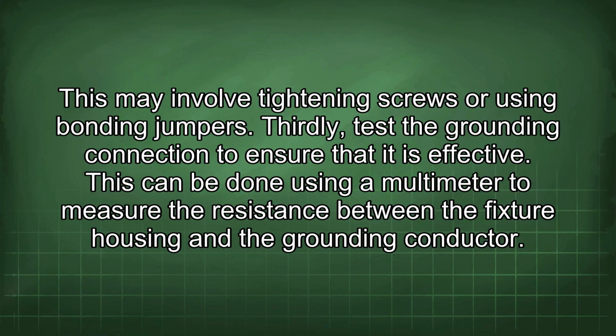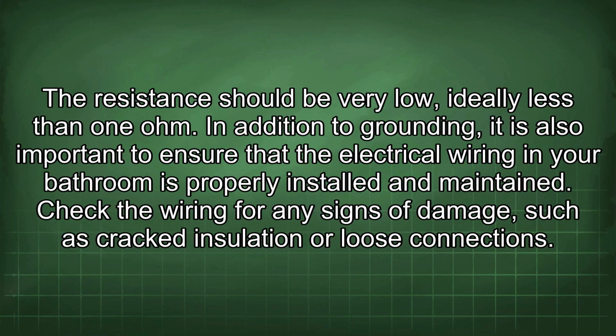Thirdly, test the grounding connection to ensure that it is effective. This can be done using a multimeter to measure the resistance between the fixture housing and the grounding conductor. The resistance should be very low, ideally less than 1 ohm.